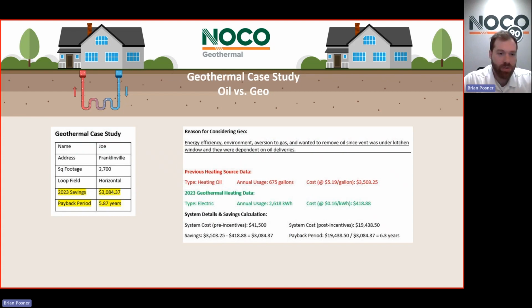Before that, he was using fuel oil. He used 675 gallons a year, and in the year that he went geothermal, the average cost of heating oil in his area was $5.19 a gallon. If he had stayed on oil in 2023, he would have spent $3,500 on heating his home. Instead, he went geothermal at the beginning of the heating season, and from the monitoring equipment on the Geo system, we know exactly how much electricity it used. His system used 2,618 kilowatt hours of electric to do his heating. Overall, that ended up costing $418. So he saved $3,100 by going geothermal.